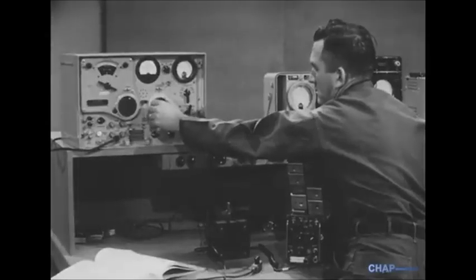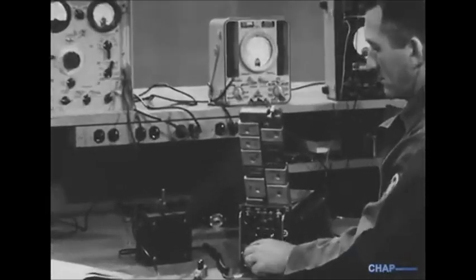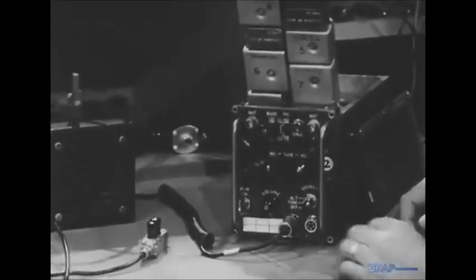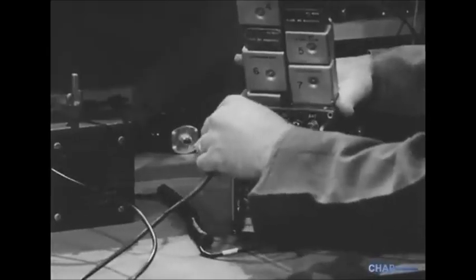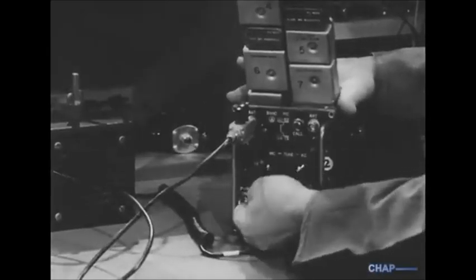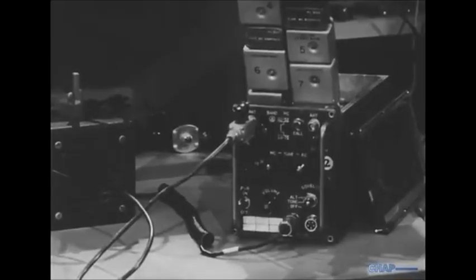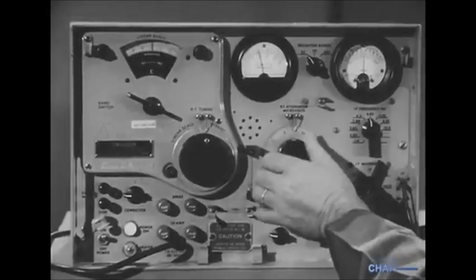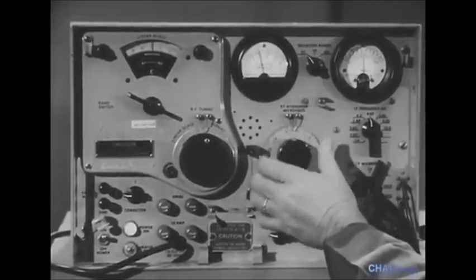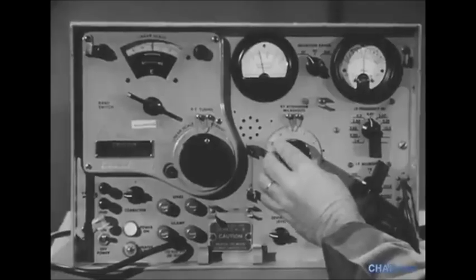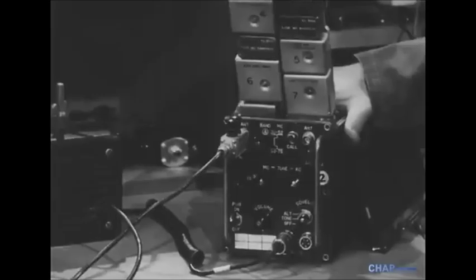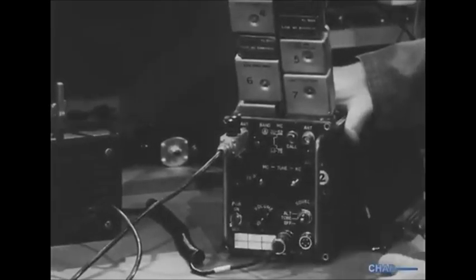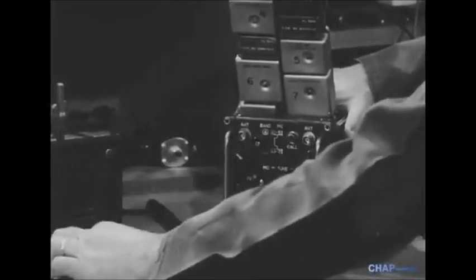Therefore, we set the signal voltage at its lowest level. We turn off the equipment under test before connecting the signal generator leads. Then we turn the equipment on, and if necessary, increase the signal strength gradually. But we don't ever try to force an output by going above the normal voltage level. Finally, we turn the equipment off again before disconnecting the signal generator leads.